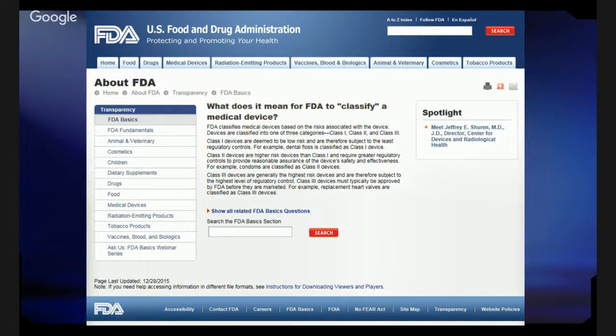Now we have to consider that surgical guides, dental surgical guides, are what are known as Class 1 medical devices, which are the lowest risk factor for medical devices and are subject to the least amount of regulatory controls. An example of a Class 1 medical device is dental floss. Of course, we're familiar with dental floss. If you look at the FDA website, a surgical guide is a Class 1 medical device because it's meant to be used in the mouth for less than an hour, as opposed to a Class 2 medical device, which carries with it a greater amount of regulatory control.